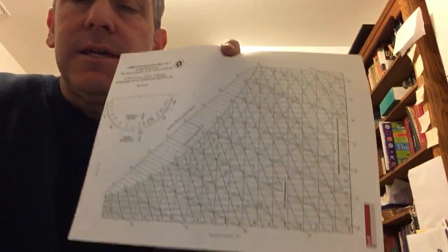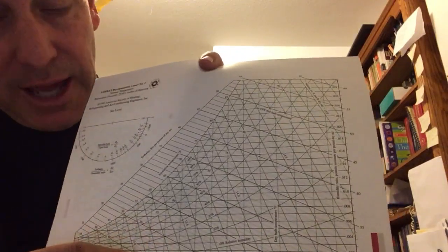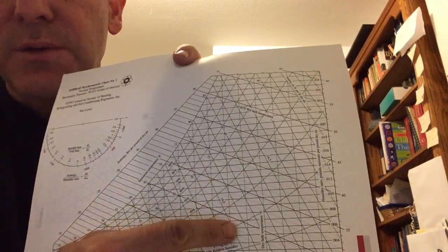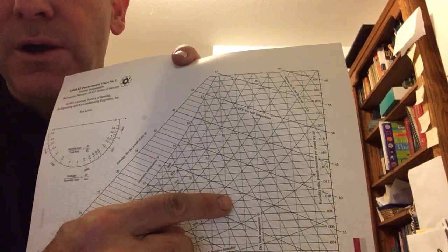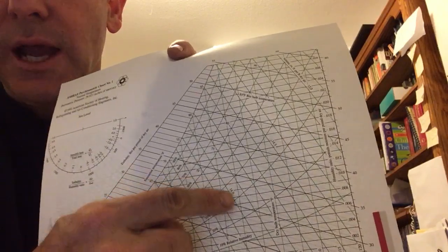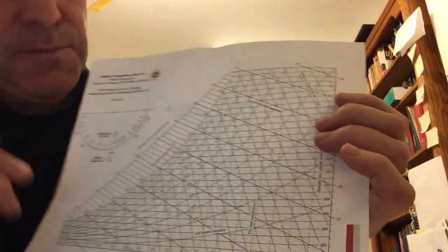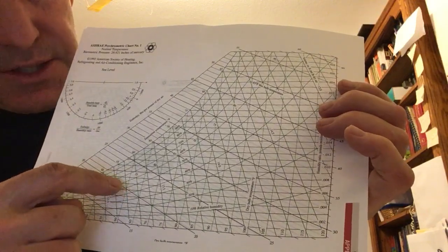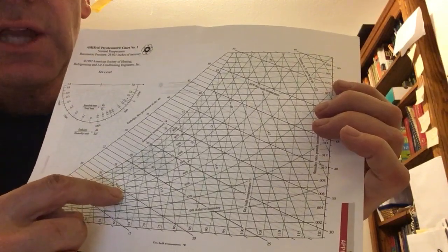The next thing is thinking about how precise we need to be if we have some dot on that chart and we get its enthalpy. If you look at these solid lines, they go in units of 5 BTUs per pound mass. If I'm somewhere in between two of these lines, I might just get some idea where it is relative to the upper and lower line, 30 and 35. But we want you to be more precise than that, and it's not that hard to do, because even though lines in units of 1 don't go through the chart, we can easily either visualize or add them.